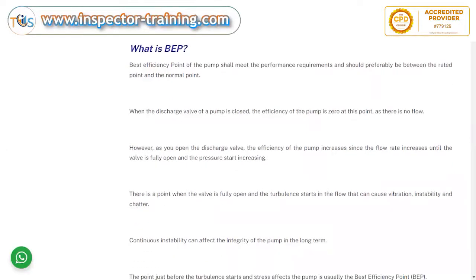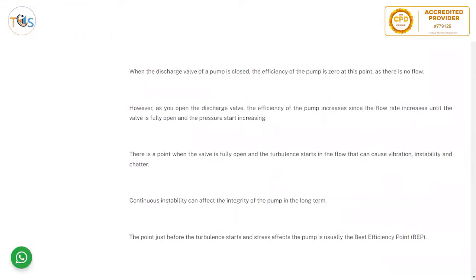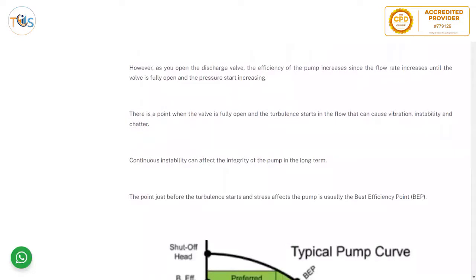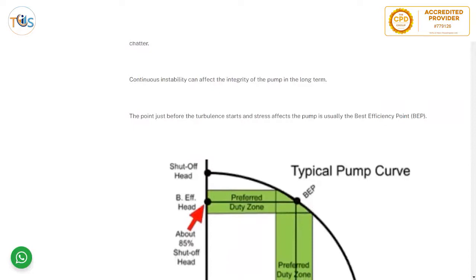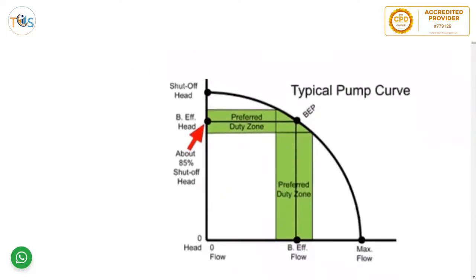When the discharge valve of the pump is closed, efficiency is zero because there is no flow. As you open the discharge valve, efficiency increases with flow rate until the valve is fully open. At that point, turbulence starts in the flow, causing vibration, instability, and chatter. Continuous instability can affect the integrity of the pump long term. The point just before turbulence starts affecting the pump is usually called the best efficiency point.